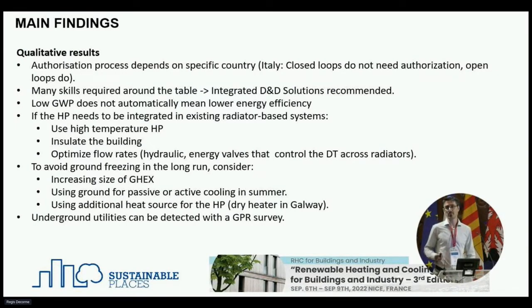And very important, if you are about to refurbish your house, renovate your house with radiators, keeping those radiators, then it is possible to go geothermal with some attention, for example, using a high temperature heat pump, which provides heat at, let's say, 55 to 60 degrees, insulating the building and optimizing the flow rates.